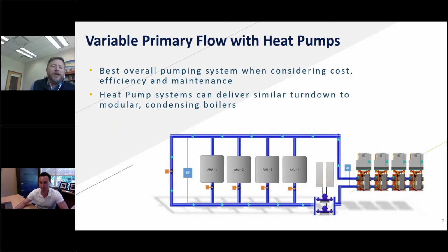So at this point, what I've talked about from an efficiency standpoint, on this slide specifically, we're talking about overall, but if I look back to air source heat pump efficiencies or boiler efficiencies, that's relevant to the unit itself, so that's not looking at pumping efficiency. It's really just looking at the efficiency of the actual prime mover. If we start looking at overall system efficiency, then yeah, whether you're looking at a variable primary system or a primary-secondary system where I have dedicated pumps inside of a boiler, or pumps for the air source heat pump, if it's a decoupled loop, then obviously you would take that into account.